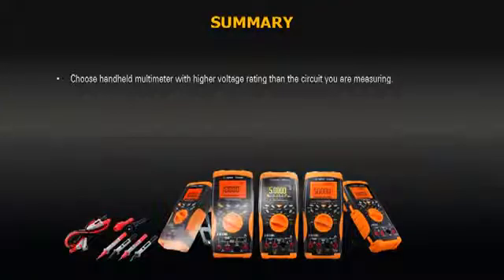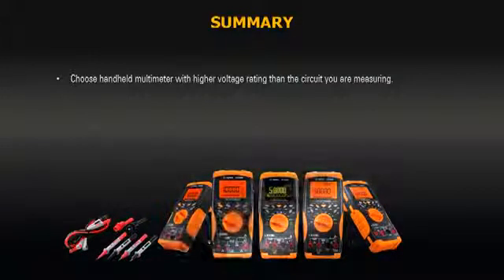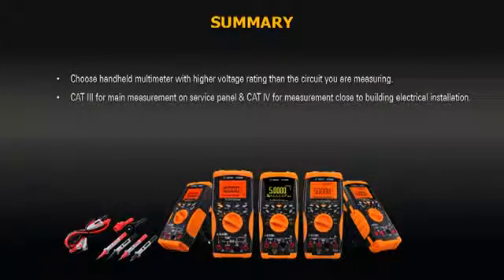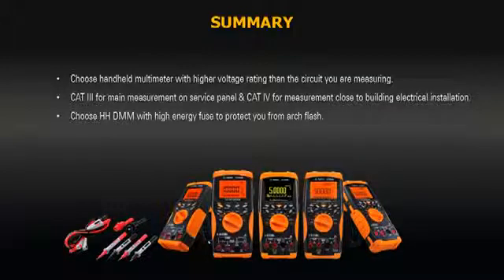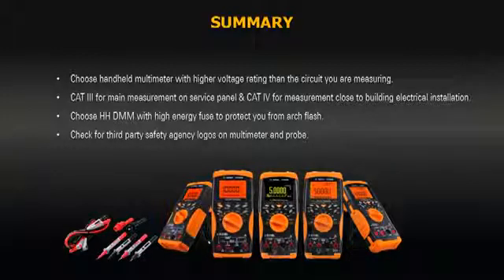In summary, to be safe, you should choose a multimeter with a voltage rating higher than the circuit you are measuring. You need at least a Cat 3 multimeter for mains measurements and a Cat 4 multimeter for measurements close to the main source. For protection against arc flash, make sure that you select a handheld multimeter designed with a high capacity fuse on the current input circuitry. Lastly, remember to check for the safety certification logos.